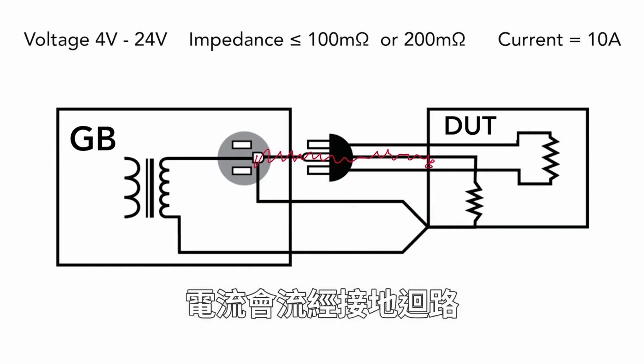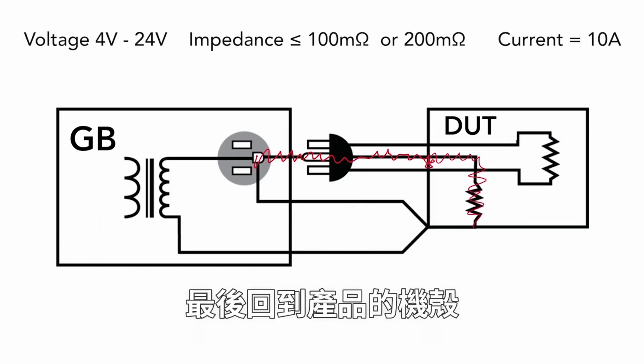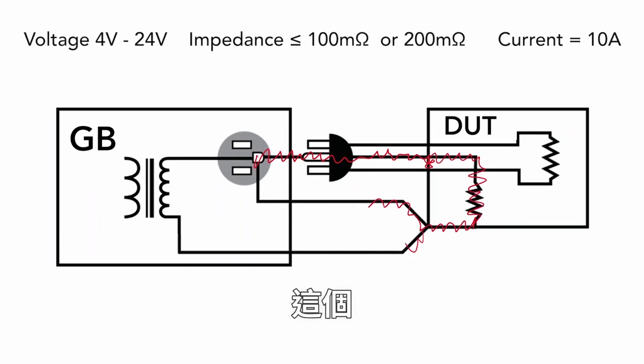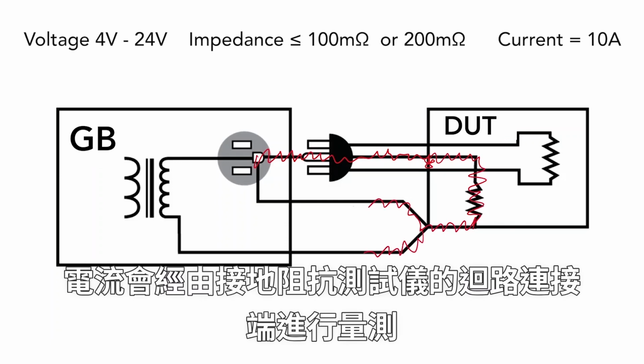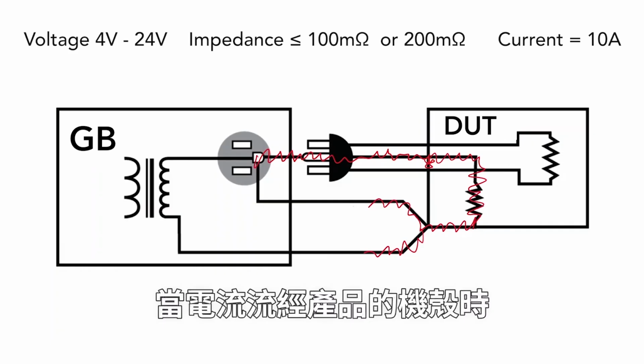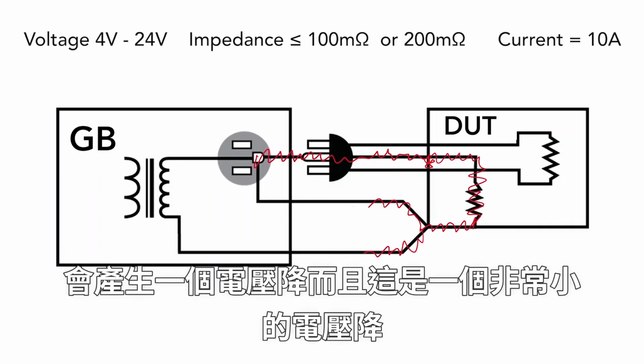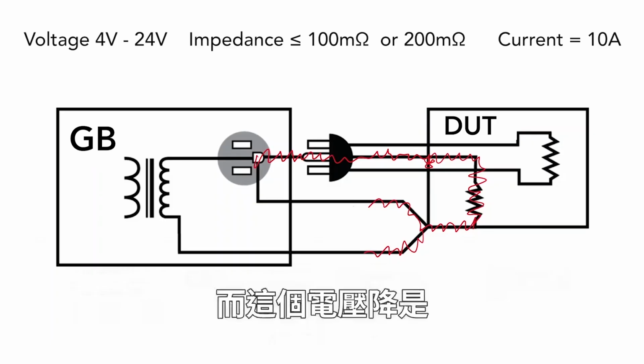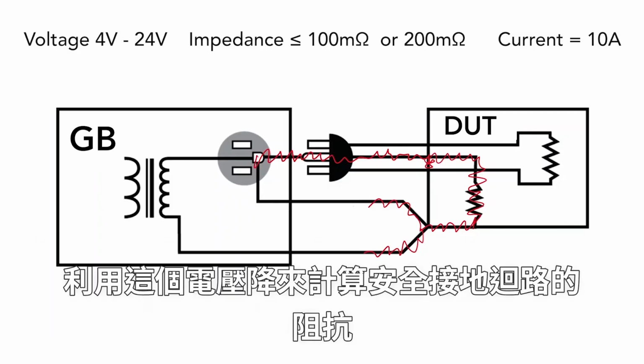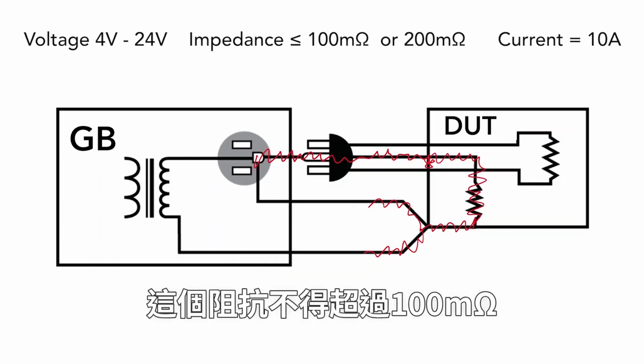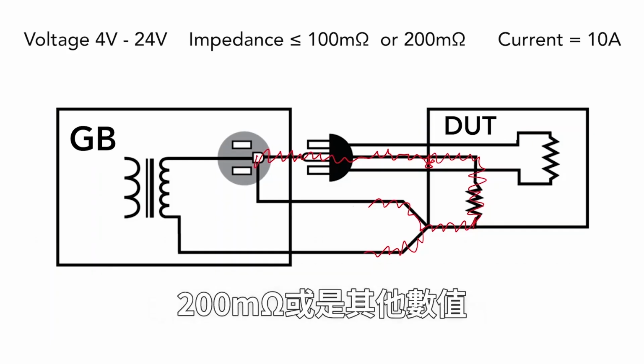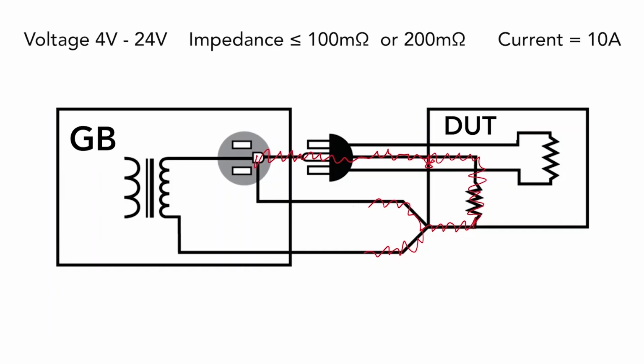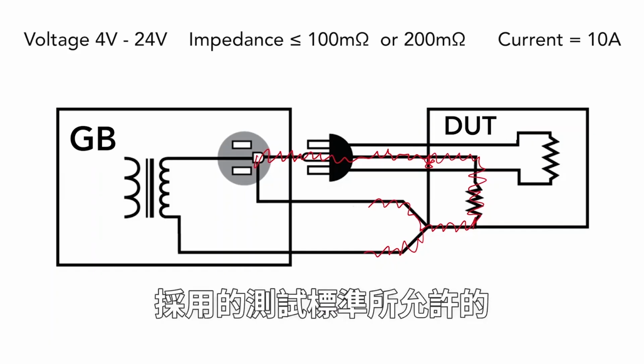Current flows through the ground circuit, makes its way all the way back to the chassis of the product, which is where it's measured via the return connection of the ground bond tester. Now, when this current flows through the chassis of the product, a very small voltage drop occurs. That voltage drop is then used to calculate the impedance of the safety ground circuit, which shall not exceed 100 milliohms or 200 milliohms or whatever number is allowed by the test standard that you're working with.